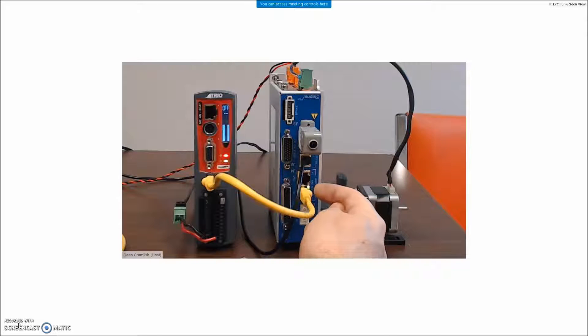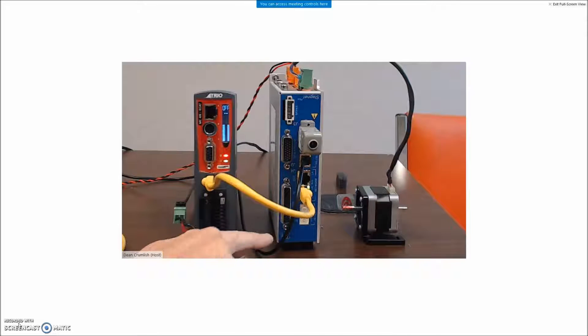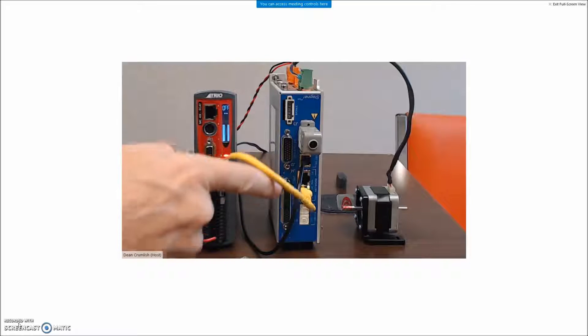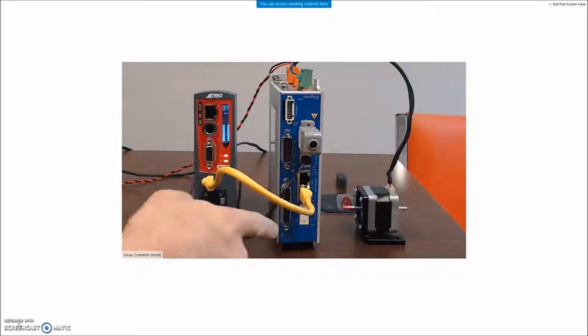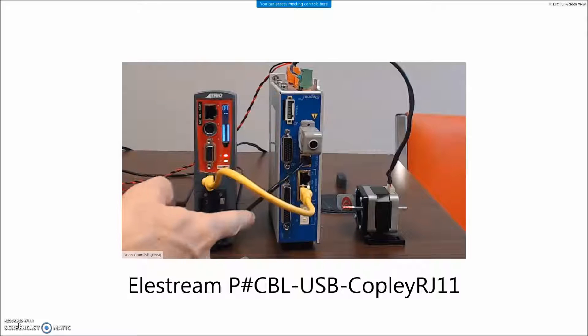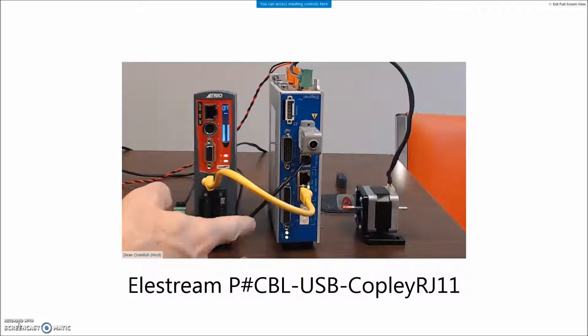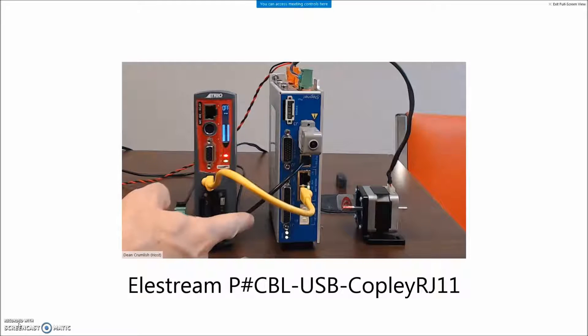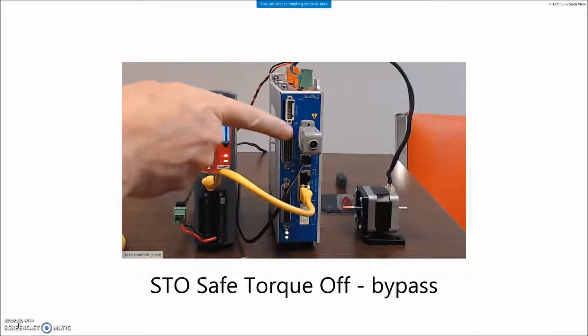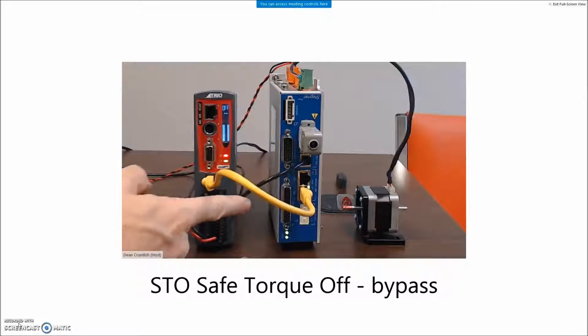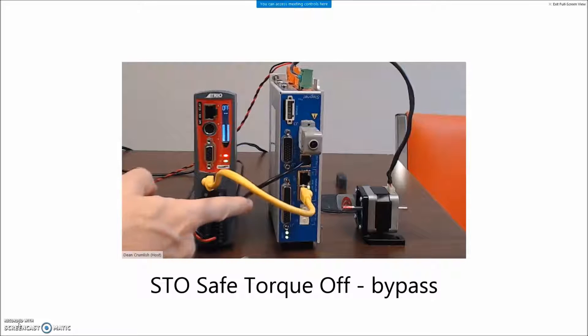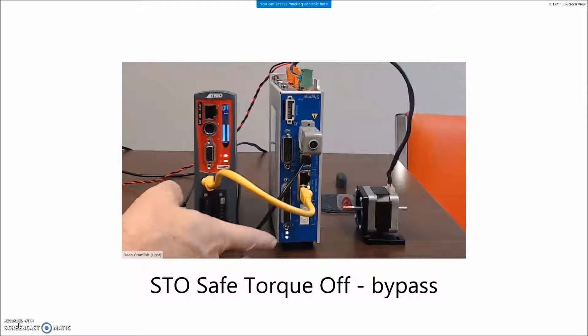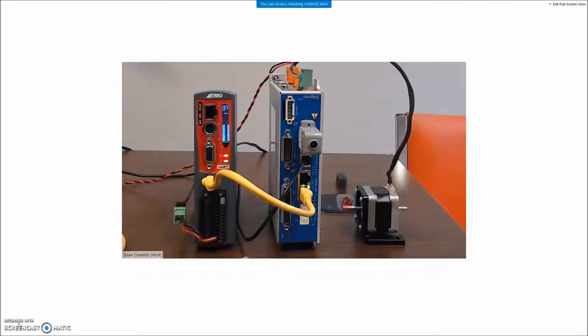I turn the power on the drive and we can see a solid EtherCAT connection and the drive is disabled with the blinking lights. There's also a serial cable. I've got a USB to RJ11 cable. The STO is connected safe torque off to bypass the safety so that I can enable the drive and the drive is waiting for the EtherCAT master to come in and enable the drive.